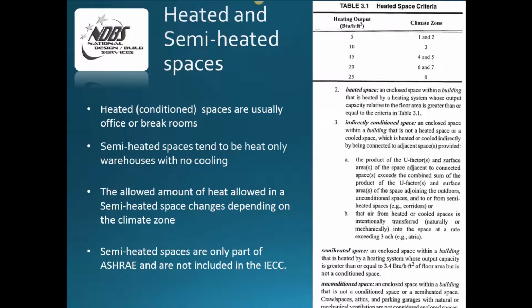So the other thing is we tend to use ASHRAE more, because ASHRAE is the code that has semi-heated spaces. The International Energy Code doesn't actually have a provision allowing semi-heated spaces. So that's why we end up with ASHRAE quite a bit more.